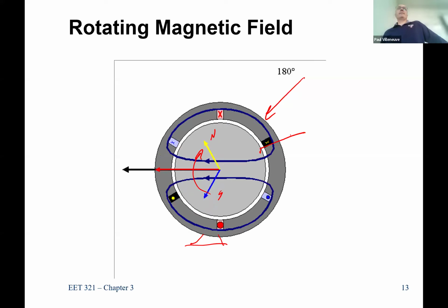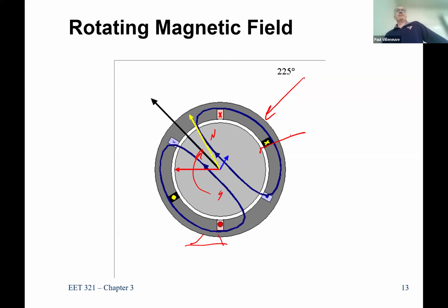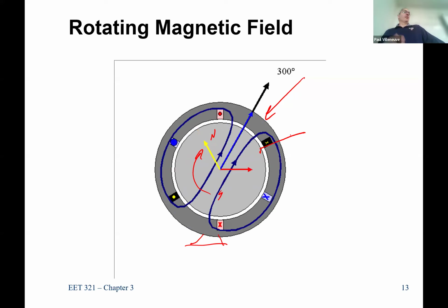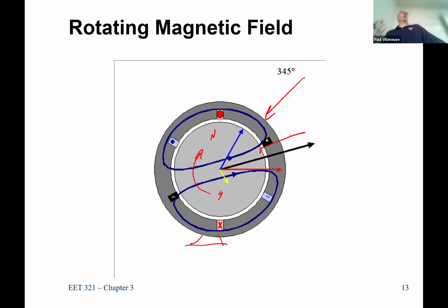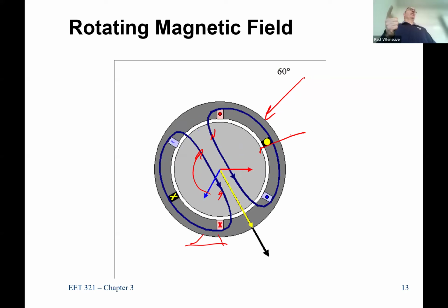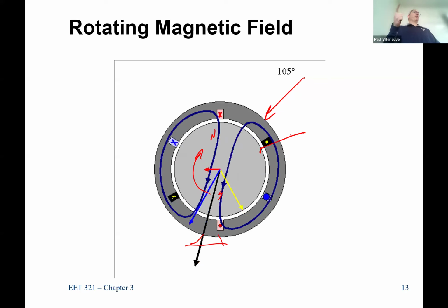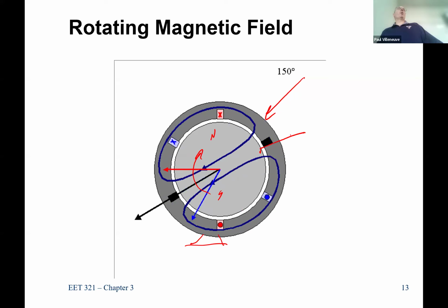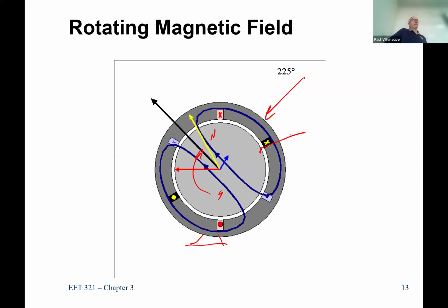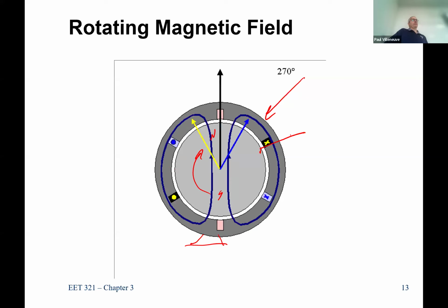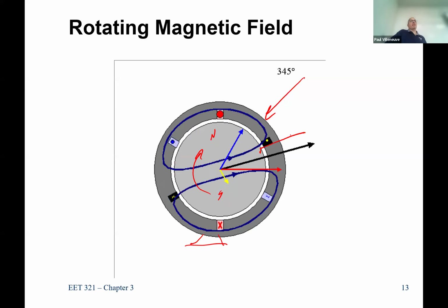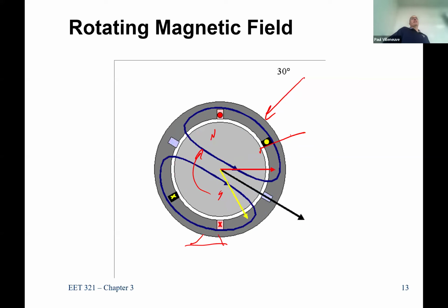So the frequency of the electricity generated would be determined by the rotation speed of the motor, right? Well, that depends. The question is, is the electrical frequency determined by the speed of rotation? And the answer is partly. If you're a generator, it's determined by the speed of rotation and the number of poles of the machine. So it's not just the electrical frequency, there are two parts to it. But it can be directly determined if it's a two-pole machine. The operating speed and the electrical frequency would be essentially the same.